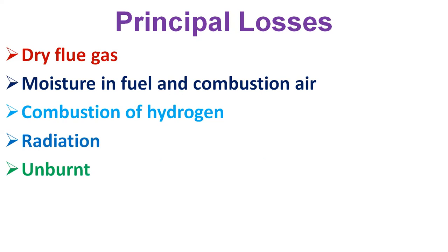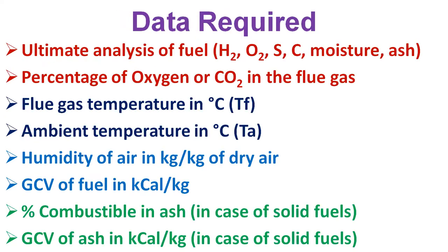The data required for calculating boiler efficiency using the indirect method includes: ultimate analysis of fuel (hydrogen, oxygen, sulfur, carbon, moisture content, and ash content); percentage of oxygen or CO₂ in the flue gases; flue gas temperature; ambient temperature in °C; humidity of air in kg/kg of dry air; gross calorific value in kcal/kg; and percentage combustible in ash and GCV of ash in kcal/kg for solid fuels.